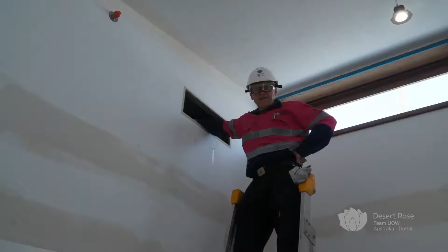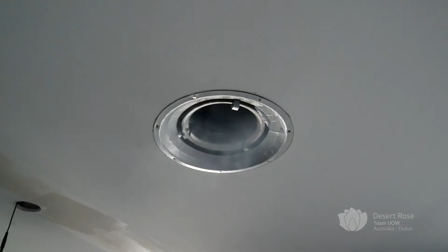We're going to do a smoke test, which is a way of finding out whether any of our ductwork is leaking. We'll put a smoke generator here and blast some smoke into this return air duct, which will then go into the air handling unit, which has a fan in it, and the smoke will then come out of some of the other diffusers. What we're trying to do is make sure there's not any leakage in the ductwork.